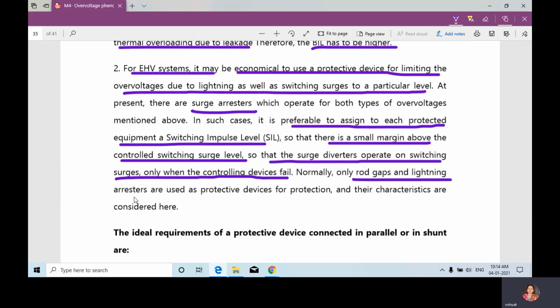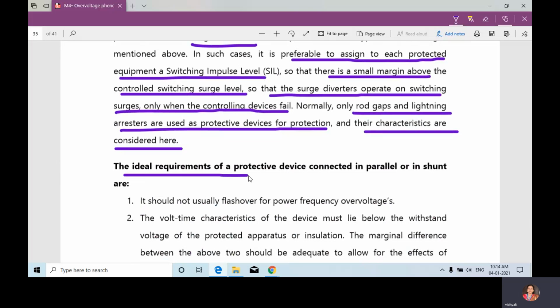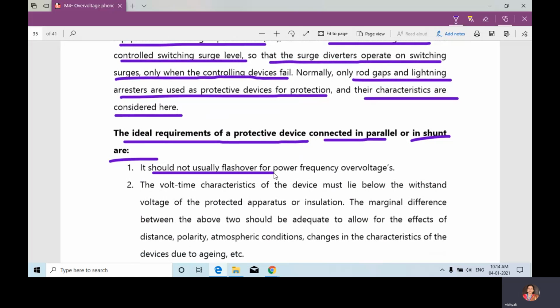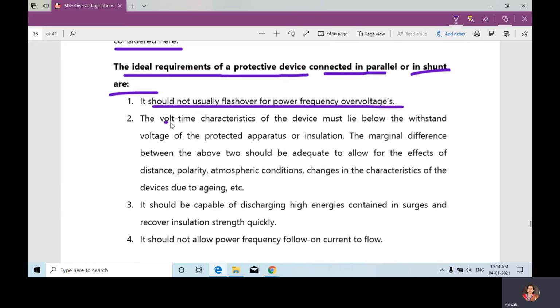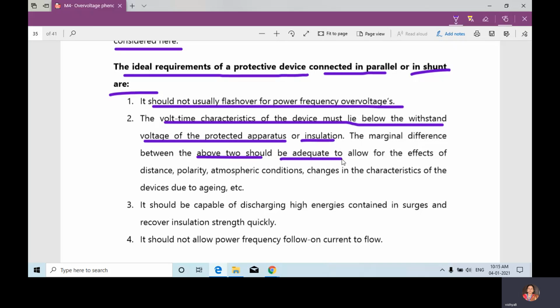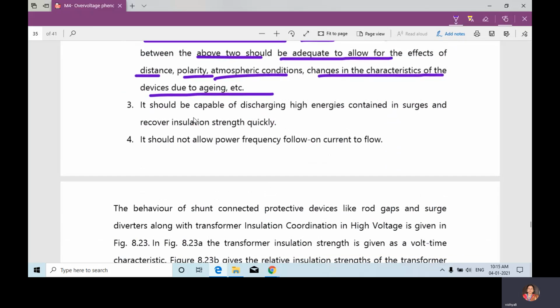Only rod gaps and lightning arresters are used as protective devices for protection, and their characteristics are considered here. The ideal requirements of a protective device connected in parallel or in shunt are: first, it should not usually flash over for power frequency over voltage, and the voltage time characteristics of the device must lie below the withstand voltage of the protected apparatus or insulation. The marginal difference between the above two should be adequate to allow for the effects of distance, polarity, atmospheric conditions, changes in the characteristics of the devices due to aging, etc. It should be capable of discharging high energies contained in surges, and also recover insulation strength quickly.